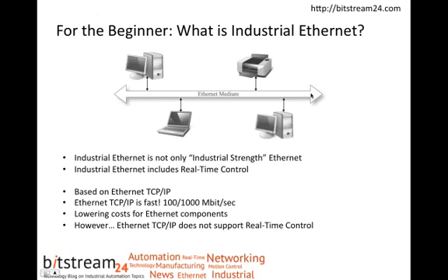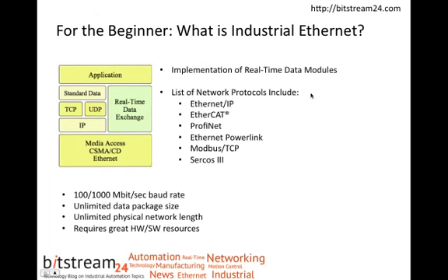However, the unpredictable nature of TCP/IP in terms of timing has been a drawback for many industrial network applications, specifically those with real-time requirements. Yet, as the overall cost versus performance has improved over time, industrial users have developed methods to overcome these apparent shortcomings. The implementation of additional real-time data exchange protocol layers or add-on software incorporated prioritization, synchronization, and other techniques to ensure the timely delivery of messages.